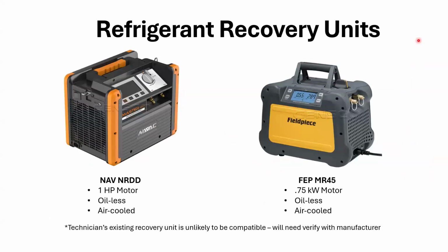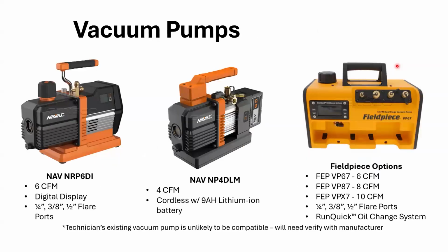Refrigerant recovery units, of course. So make sure they're rated for the 454B. This one's been out for a little while now, maybe 2 or 3 years, and it was rated for 454B already. So there's a chance that tools that are 3 to 5 years old were already ready for it. Vacuum pumps, same thing. A decent CFM rating, between 3 and 9 is good enough on those pumps.